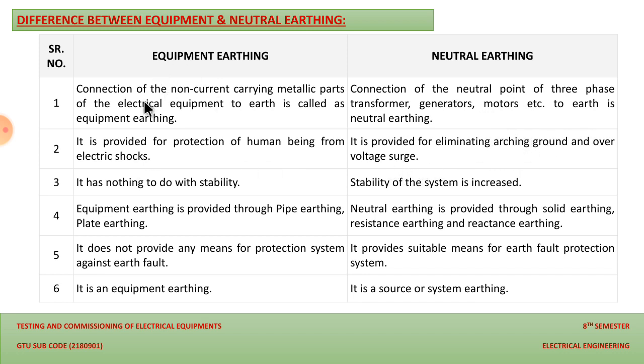And the third point in the equipment earthing is it has nothing to do with the stability, because a simple wire which is provided is not helping in the stability of the equipment, and through the neutral earthing we can provide the stability to the system. So stability of the system is increased just because of the neutral earthing, and we can eliminate the unwanted surges and arcing ground with the help of neutral earthing, so that the stability of the system will increase.